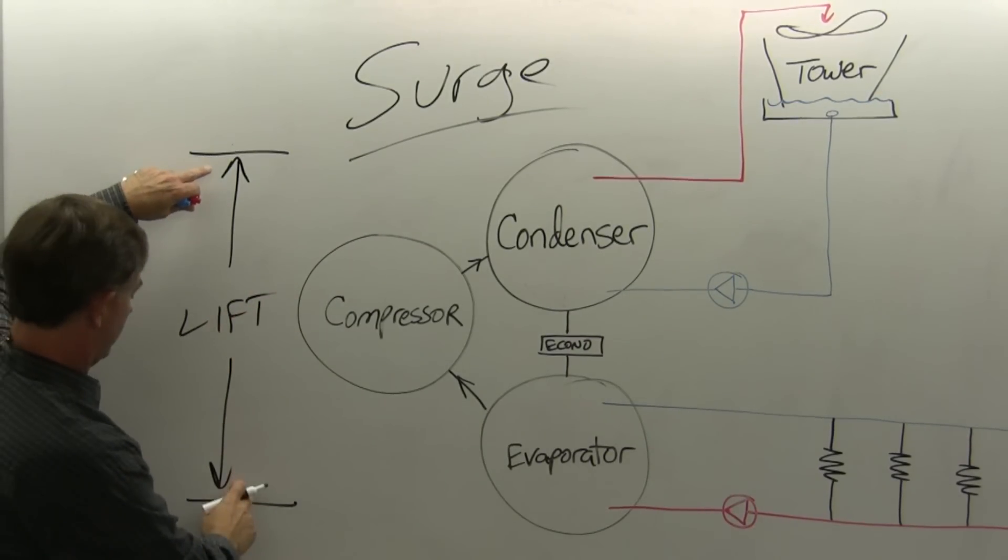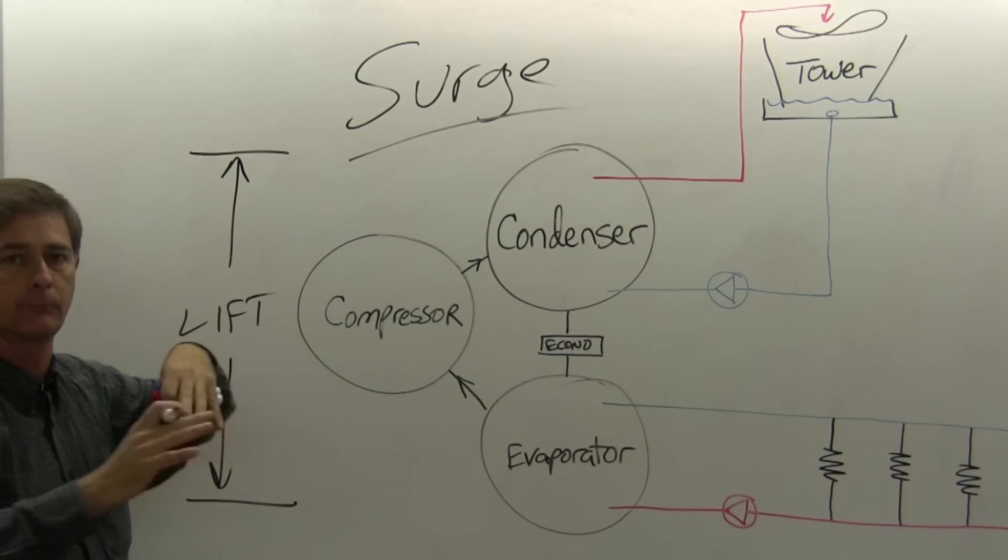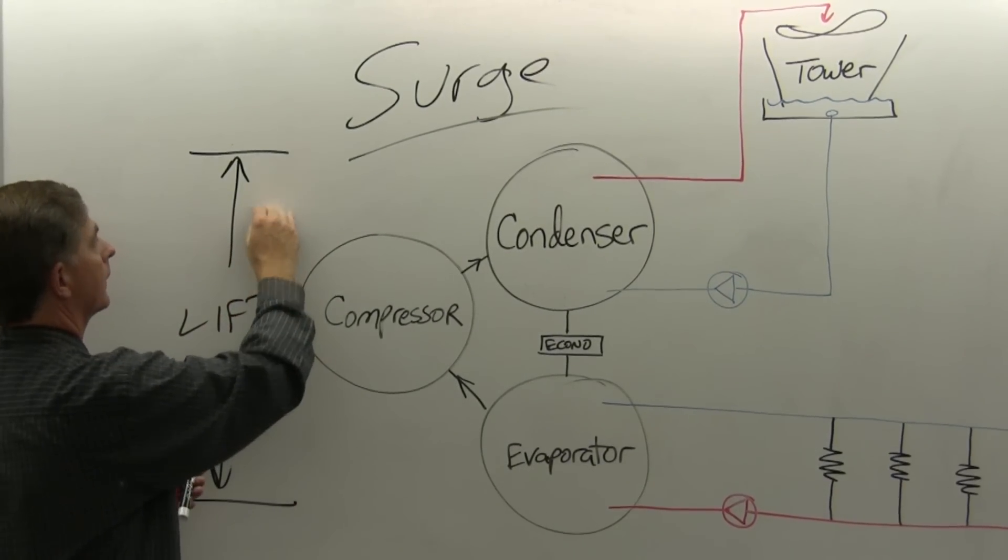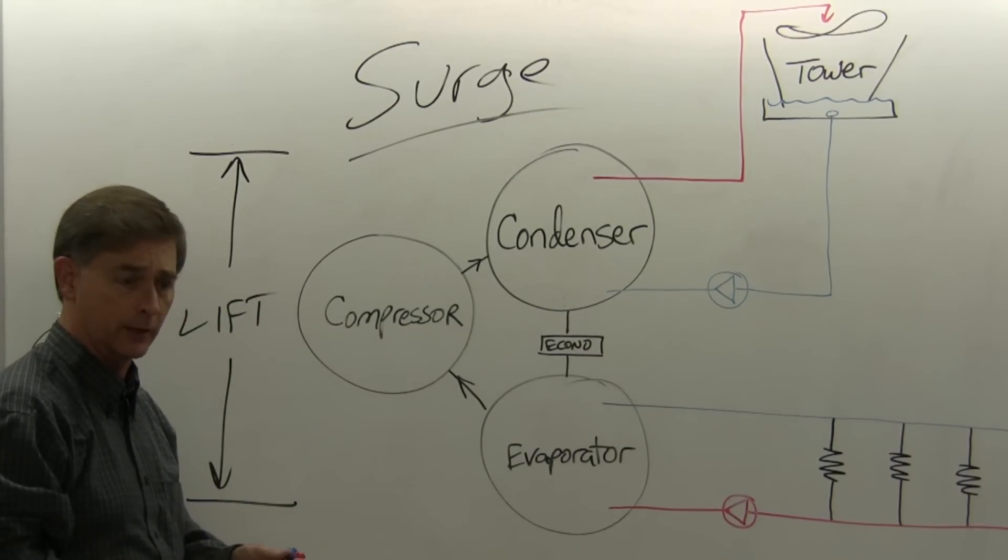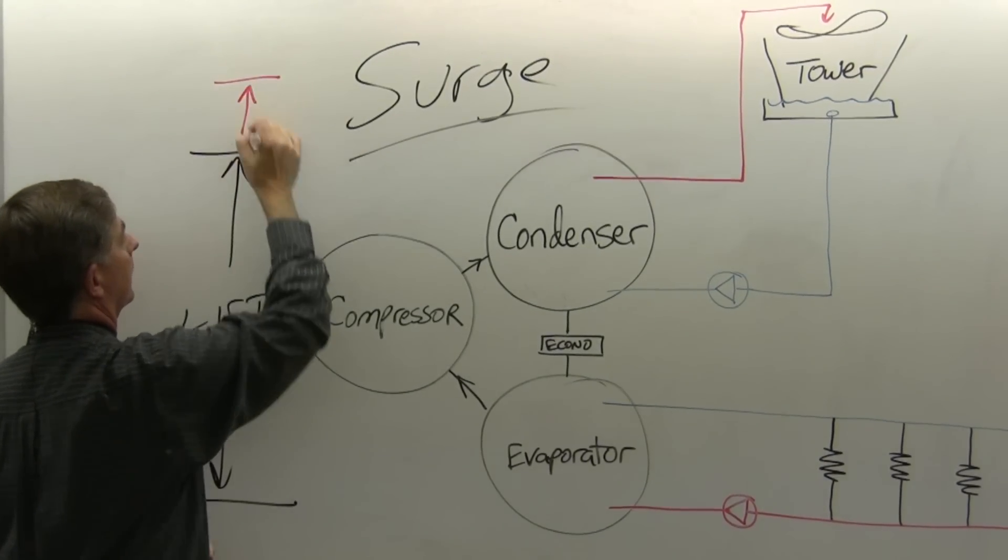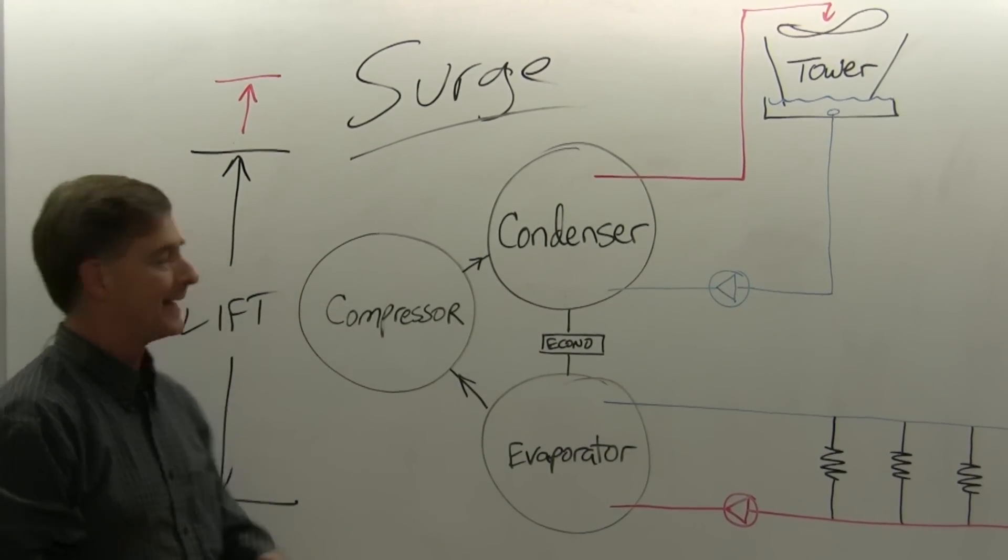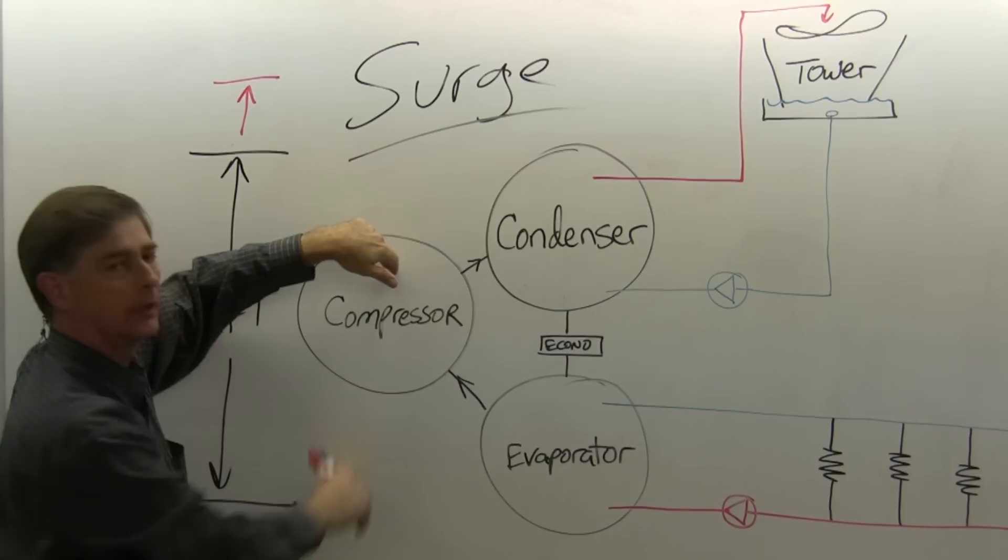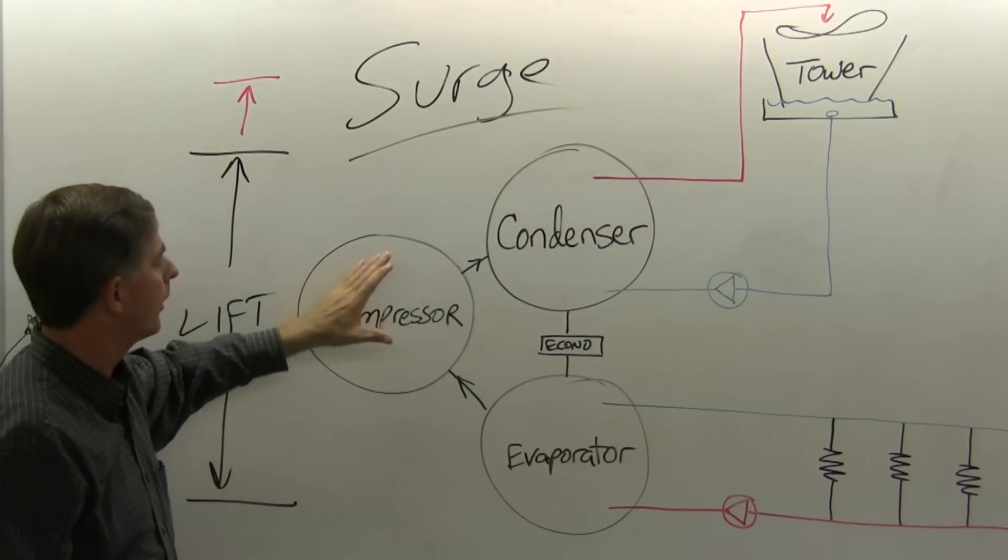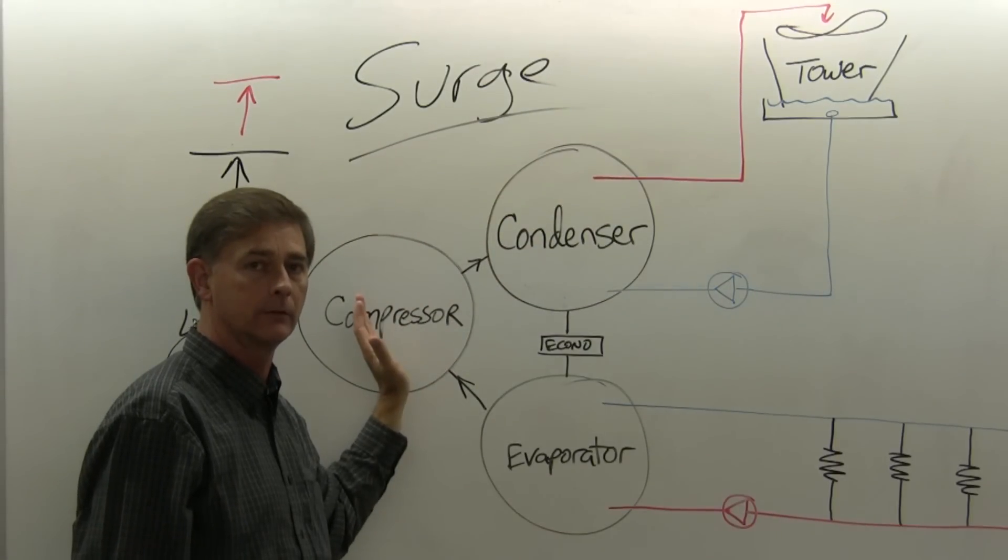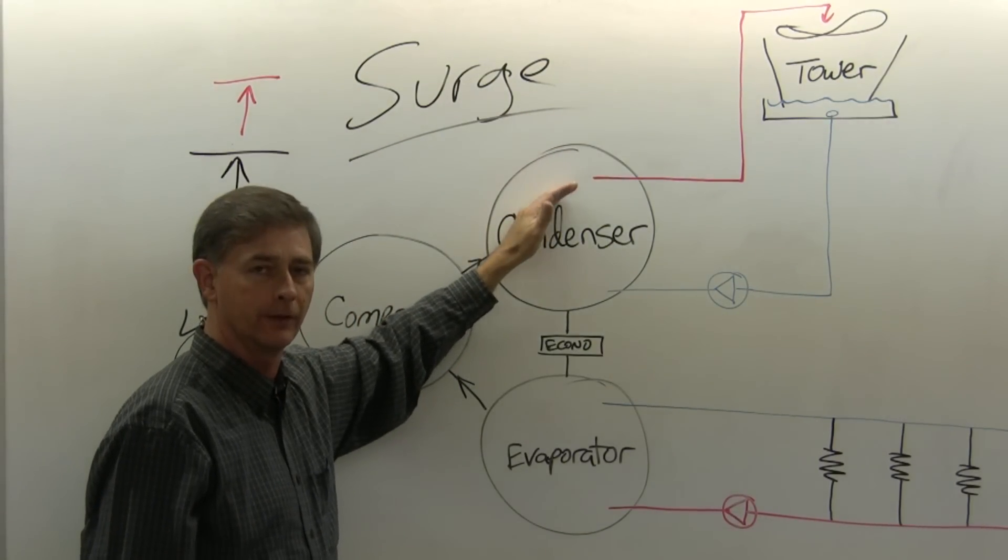Now this compressor is designed for a particular range of pressure differential. If that pressure differential goes up, an increase in pressure differential, if it gets to the point where the pressure differential exceeds the pumping capacity of this centrifugal compressor, then what happens is this compressor can no longer lift the refrigerant pressure to this high pressure.